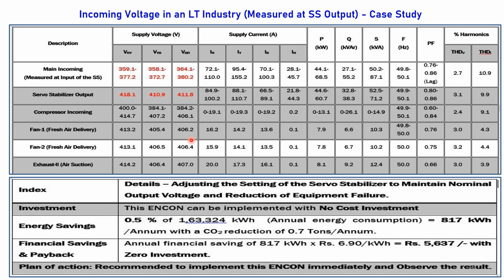Even there is a control mechanism to adjust the voltage. There may be a slight failure in the control system, or some contact applicable to the variac and all those things. So we insisted the company check with an OEM, and they immediately arrested the problem in the system, and we ensured that there is 0.5% saving for the overall percentage, but they got 0.22% saving because of that voltage. We recently got it, and next week I'm going to take the reading, and if possible I can also present the reading in the next presentation.